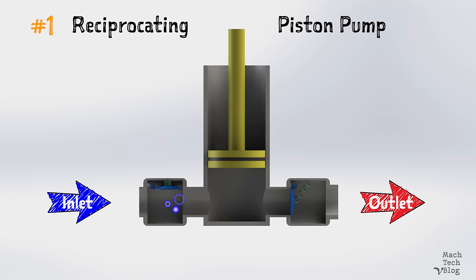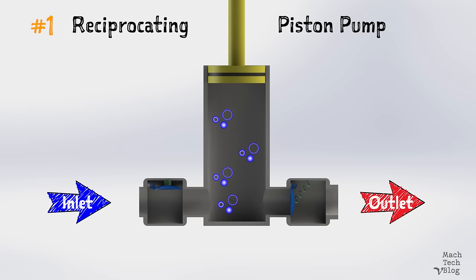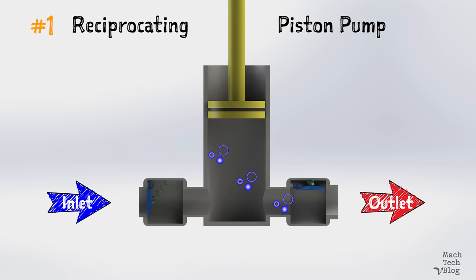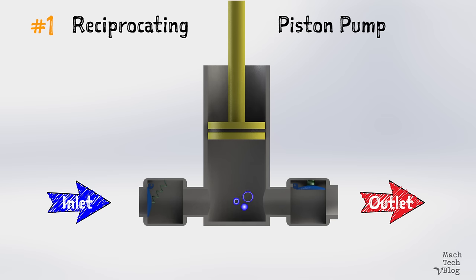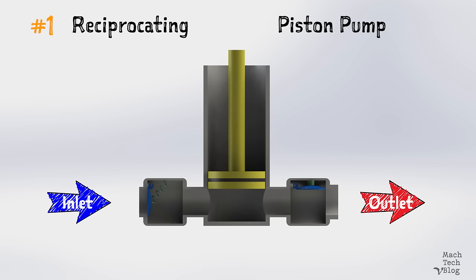As the valve on the suction side of the pump opens, the valve on the discharge side closes. On the discharge stroke, which is the downstroke here, the piston pushes on the fluid in the cylinder. The pressure rises. The suction valve now closes and the discharge valve opens to release fluid into the system.